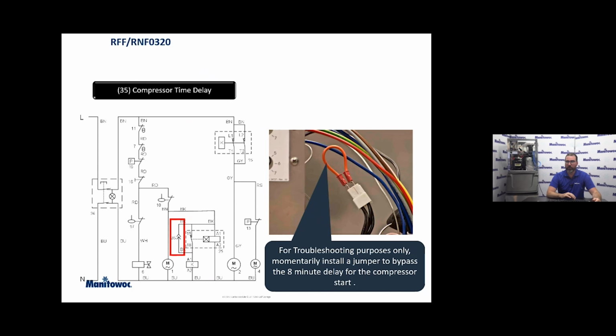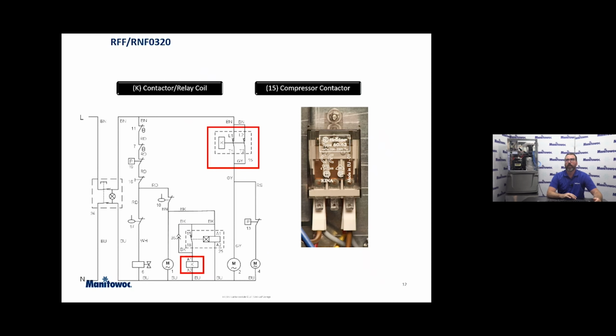Here's a picture of that jumper that I was talking about earlier. As you can see, the black wires and that white connector there. Here we just have a piece of wire with 2 spade terminals on it. You could use a paper clip, something of that variety, to do the same thing. So once that time delay expires with that solid state timer, you can see that it's energizing K, circled in the small red box on the bottom. That's basically the coil for the compressor contactor. That's going to pull our contactor in, and we should be off and running into the races.